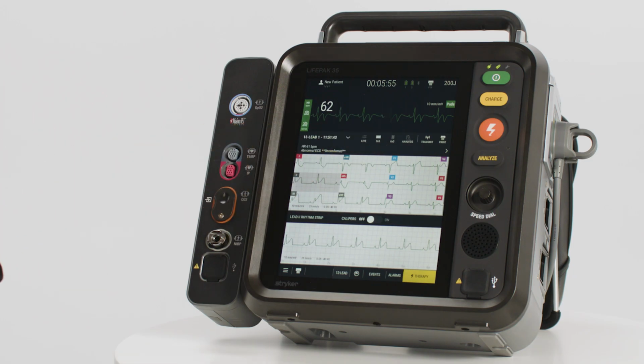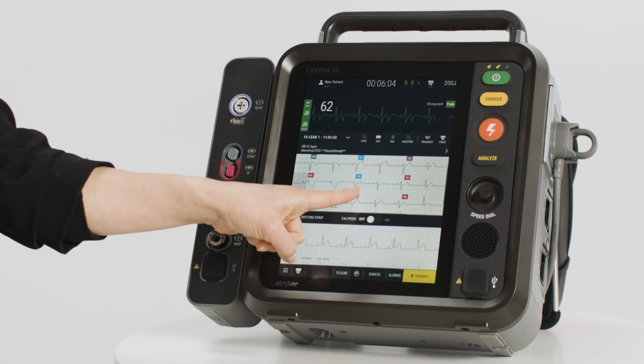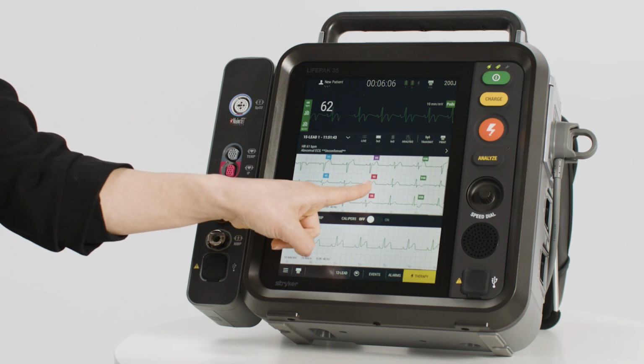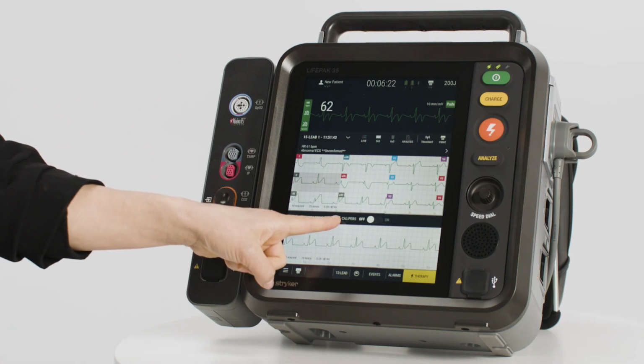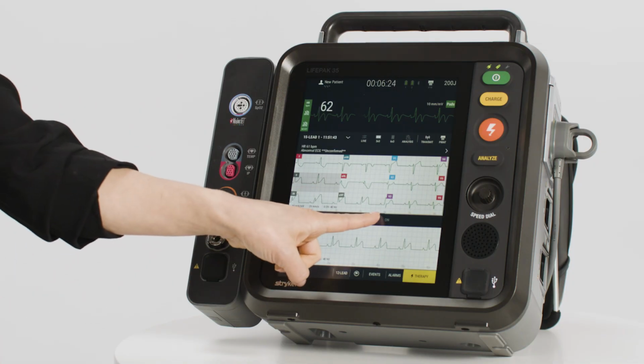When viewed in 3x4 or 3x5 format, the 12-15 lead report generates a selectable 10-second rhythm strip. The 10-second rhythm strip offers on-screen ECG calipers which can be used to compare ECG intervals and waveform durations. To activate the calipers, press Calipers On.